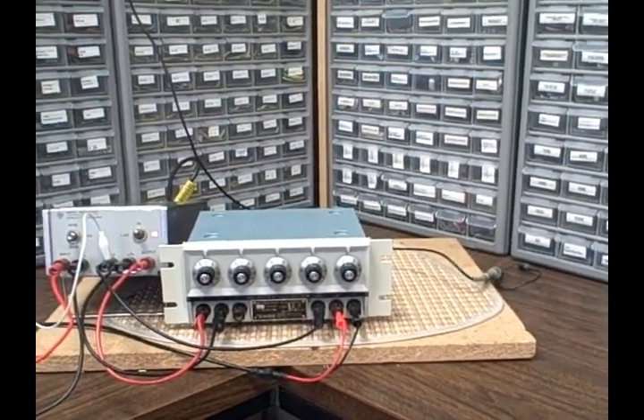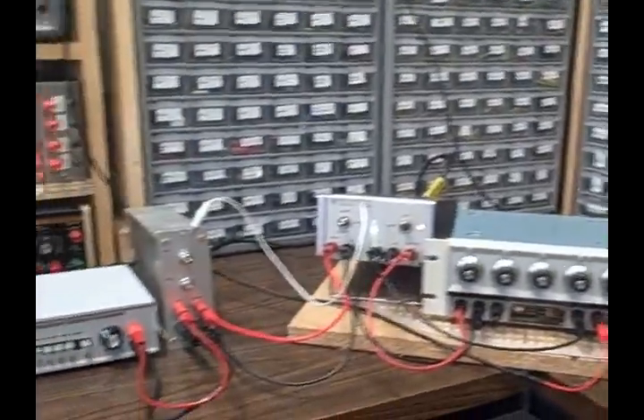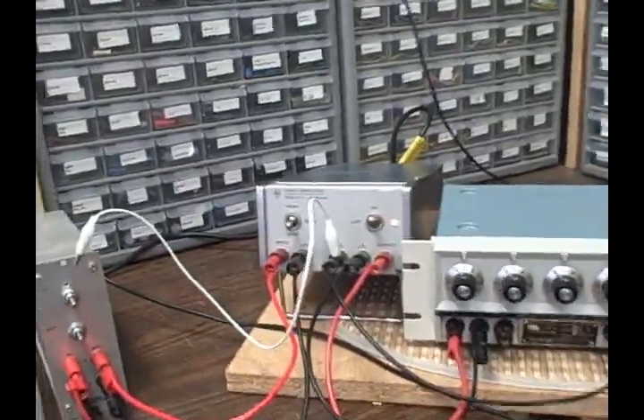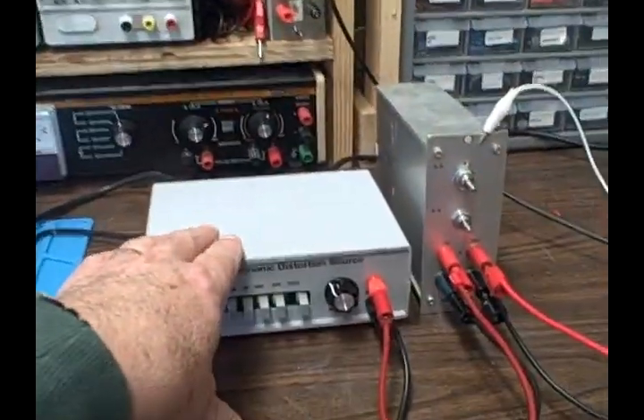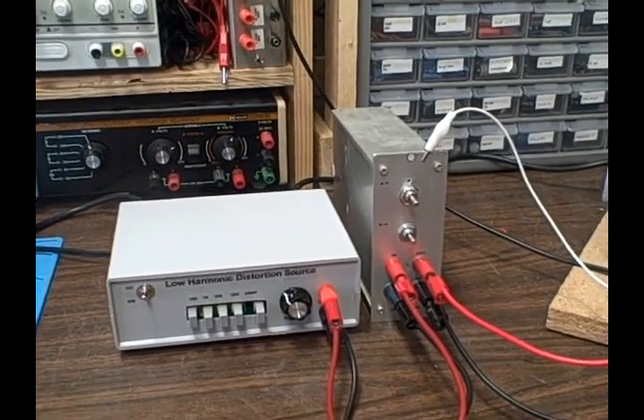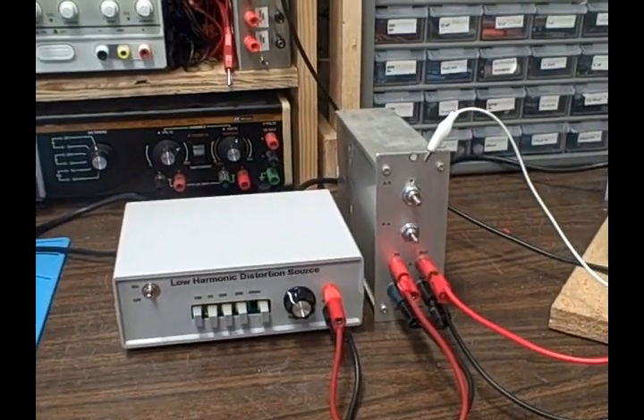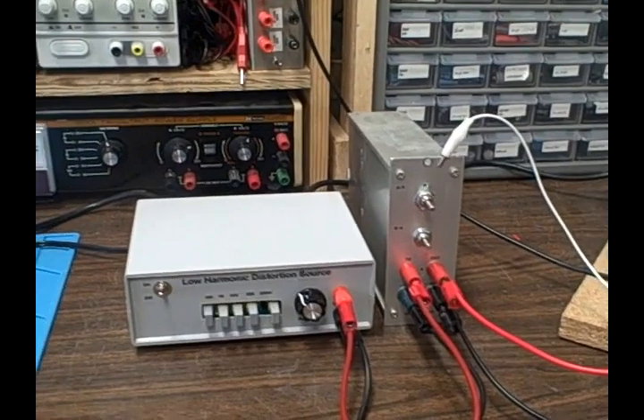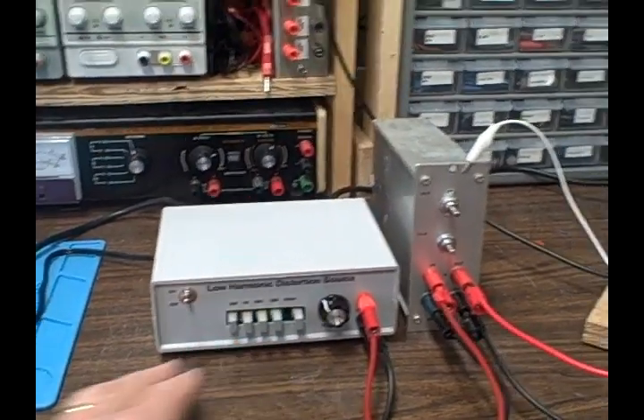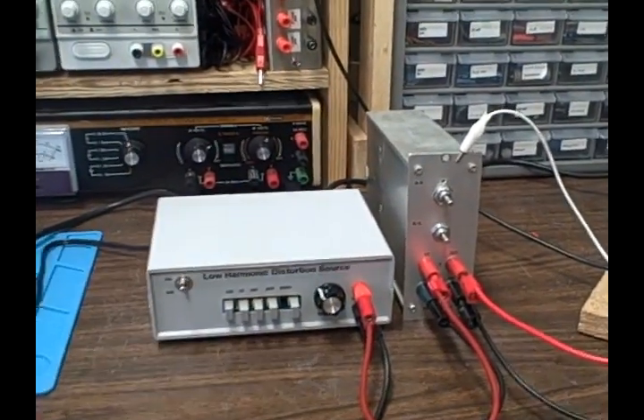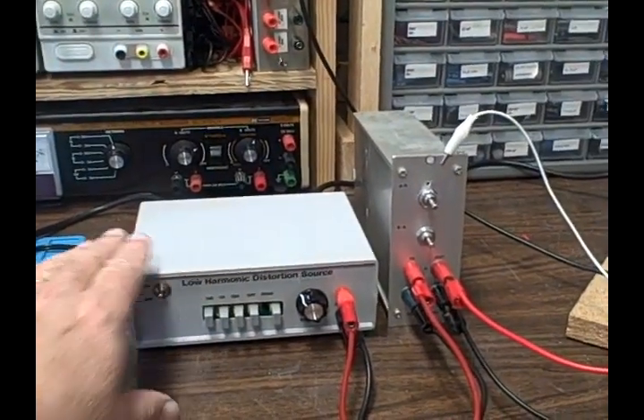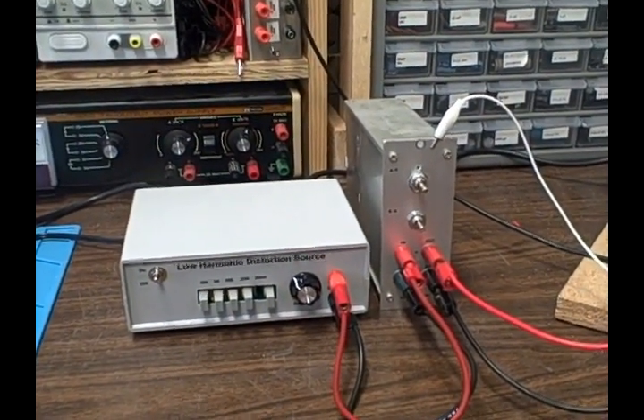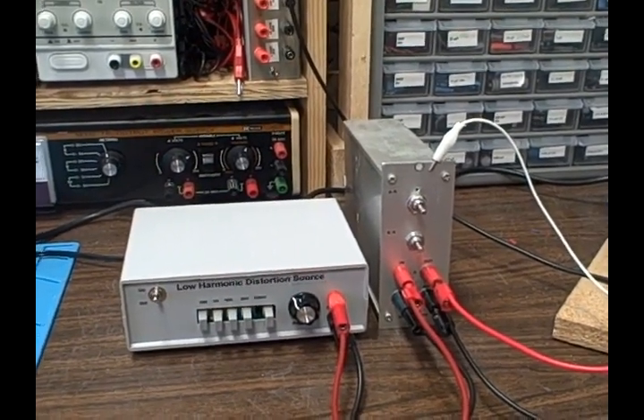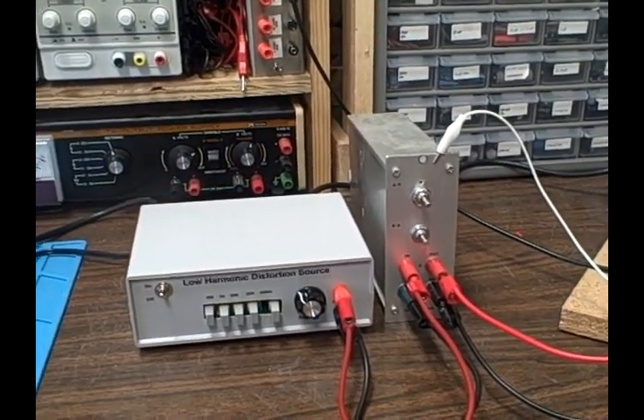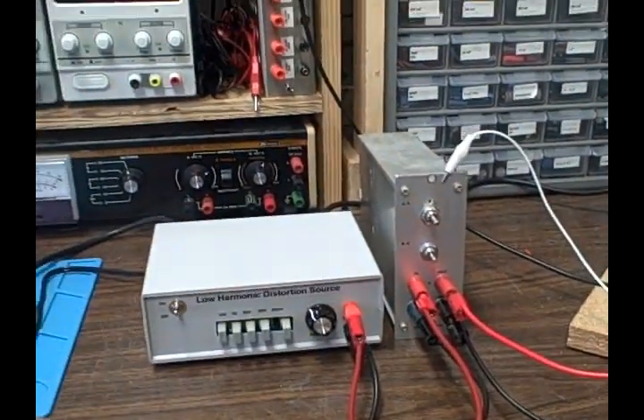And often I found that they are involved in AC calibration devices. Generally, in an AC calibration unit, you've got a couple of major components. First of all, you've got a signal source. You want that signal source to be stable, primarily. And it's nice if you can have variable frequency, which I do on this, and low harmonic distortion. This is a low harmonic distortion signal source that I built intending to use for analyzing harmonic distortion on amplifiers, but in this case it's going to work just fine to provide my base signal for this calibration unit.